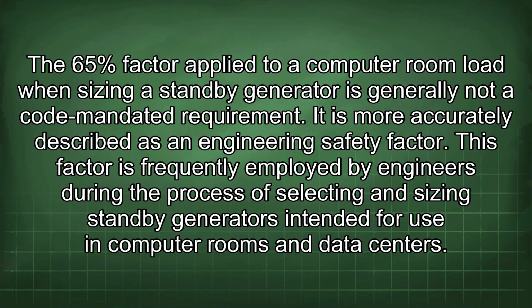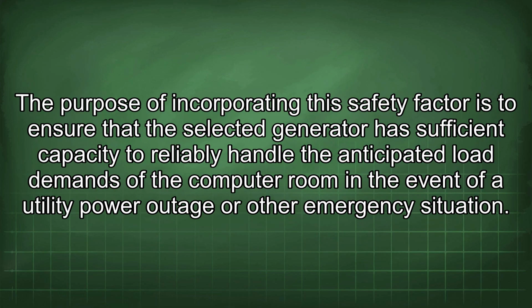The 65% factor applied to a computer room load when sizing a standby generator is generally not a code-mandated requirement. It is more accurately described as an engineering safety factor. This factor is frequently employed by engineers during the process of selecting and sizing standby generators intended for use in computer rooms and data centers. The purpose of incorporating this safety factor is to ensure that the selected generator has sufficient capacity to reliably handle the anticipated load demands of the computer room in the event of a utility power outage or other emergency situation.